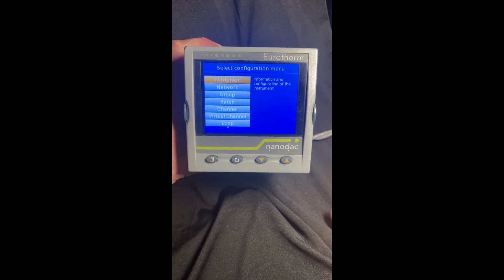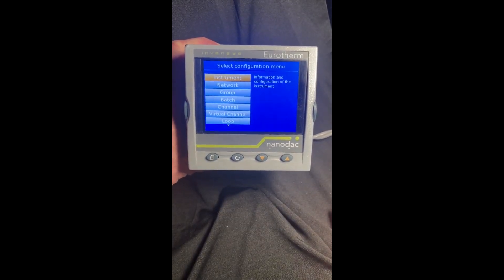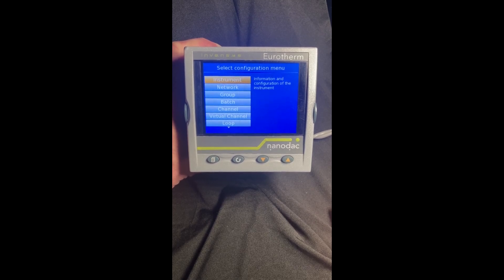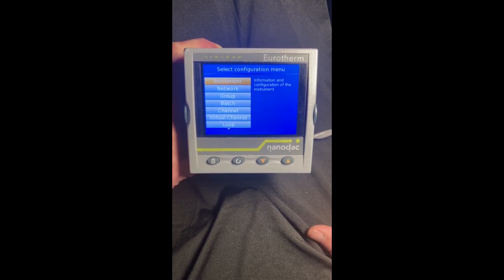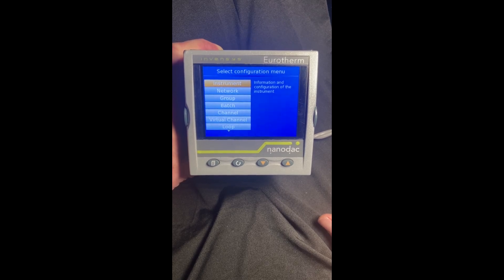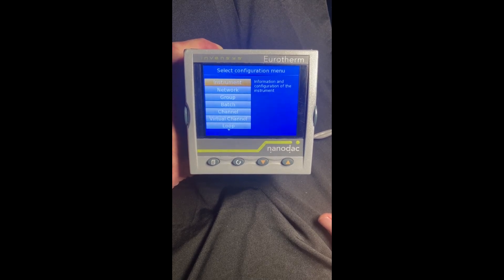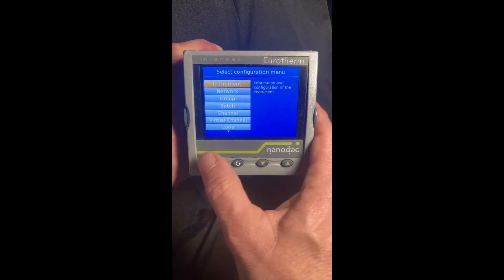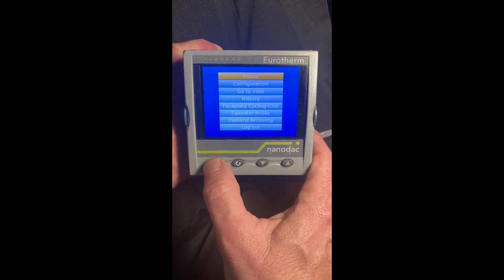One thing about the configuration level: when you're in configuration, the controller does not control the process anymore — the outputs are locked out as a safety measure. That's why when we come back to iTools I'm going to show you how to set up a supervisor level as well. Anyway, we're going to hit the page key and go back to the home menu.